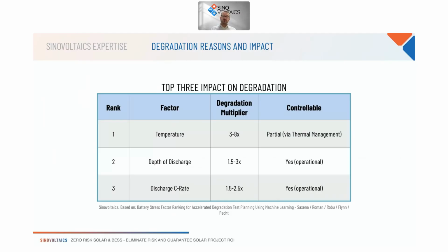Now I would like to jump to the top 3 impacts on degradation, the topic of our webinar today. Ovais covered the depth of discharge and the C-rate function, which is mostly operationally controlled. I would like to focus especially on temperature, which has one of, if not the largest, impact on the degradation of your asset by far. Looking at degradation, the multiplier could be anywhere from 3 to 8 times higher than the baseline. For the baseline, typically suppliers look at the 25°C line. This should be kept in mind throughout the presentation.